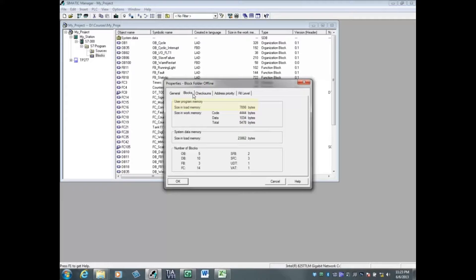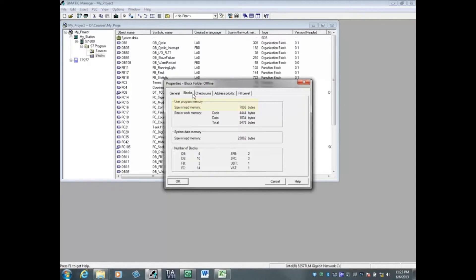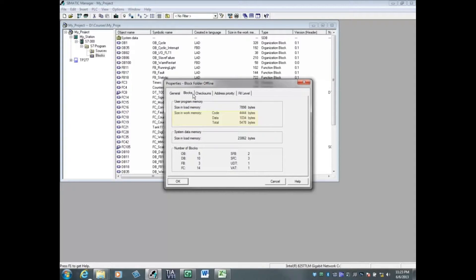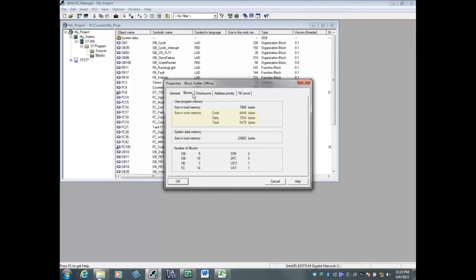7,898 bytes of load memory gets downloaded to the micro memory card or MMC. The load memory is part of the user program and is the non-volatile RAM. Work memory is the high-speed memory of the PLC which contains only the executable information and is a subset of the load memory.